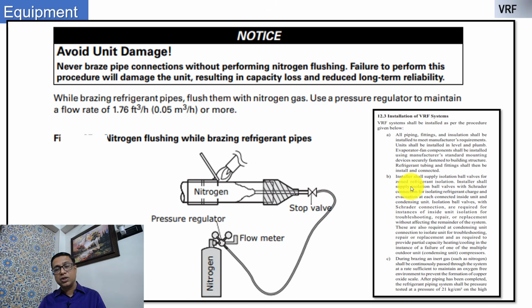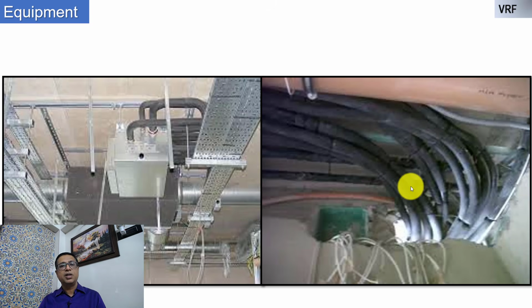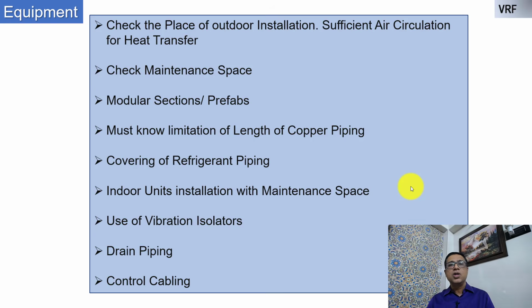Always use nitrogen for flushing while brazing the copper pipes, right? And that is very important when it comes to VRF. Here is some of the refrigerant piping. So it is very important to understand the place of outdoor installation. There has to be sufficient air circulation. There has to be proper maintenance space, right? And try to use more and more modular prefab sections to install your equipment.